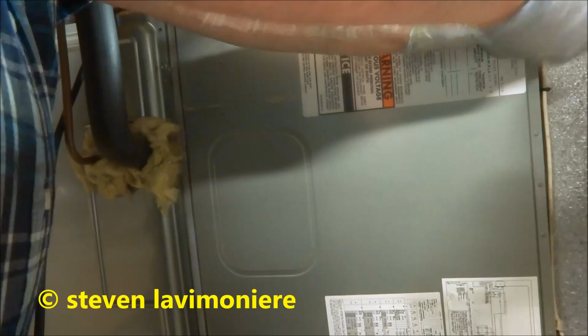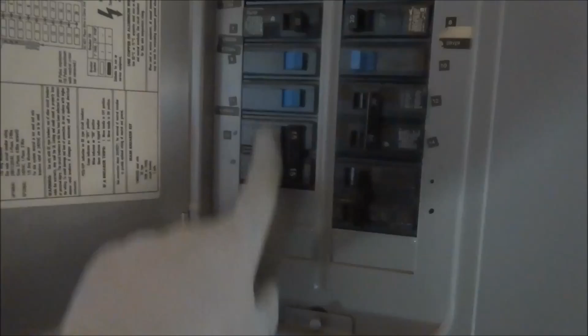I got the thermostat off. I'm gonna go put the contactor in outside, and then this thing will be fine, ready to go. I got the thermostat off downstairs, so it's not going to come on until after I change that contactor. I got the contactor right here. I know that box has got a lock on it, so I'll just shut it off here. That should be the one for the outside unit right there, the 30, or one of the two. The 15, that would be the air handler.